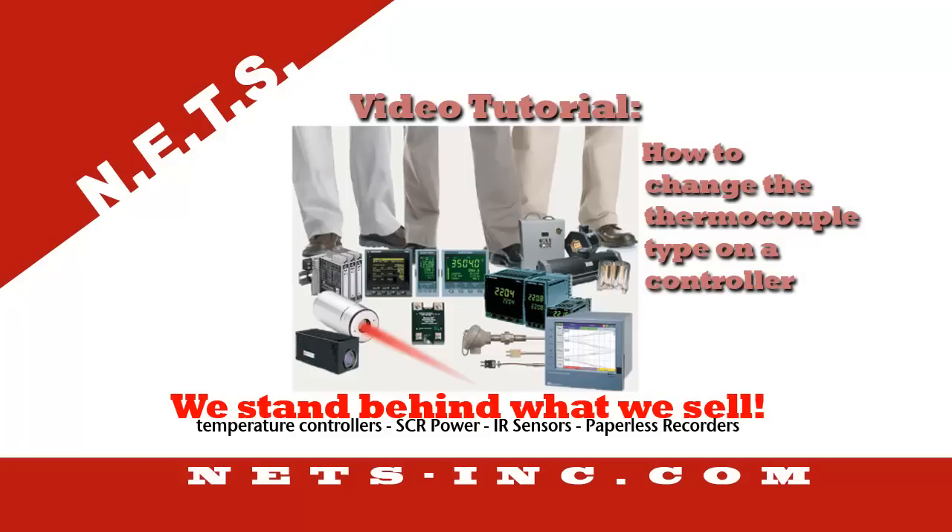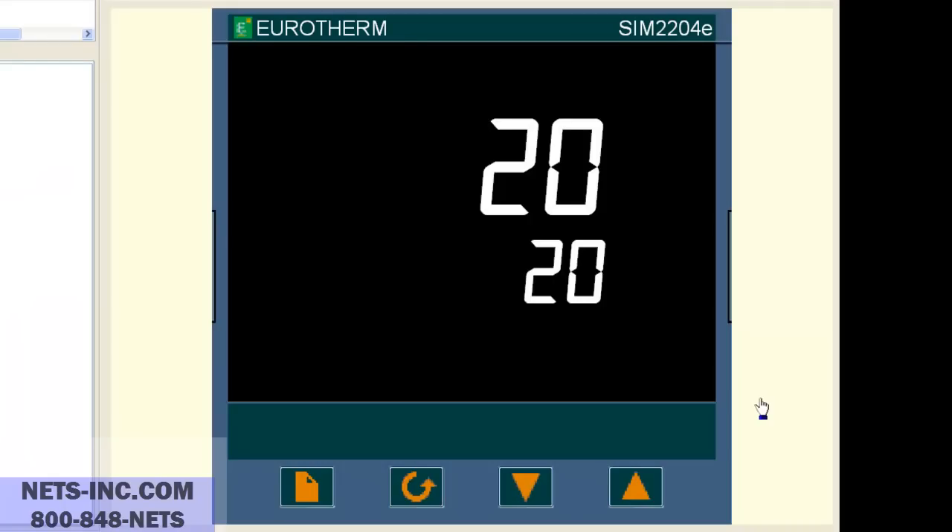How do I change the thermocouple type on my controller? This video tutorial will show you how to change the thermocouple type on a Eurotherm 2200 series controller. Presently the controller is set up as a type J thermocouple with a range of 0 to 600 degrees C. We are going to change it to a type K thermocouple with a range of 0 to 1372 degrees C.